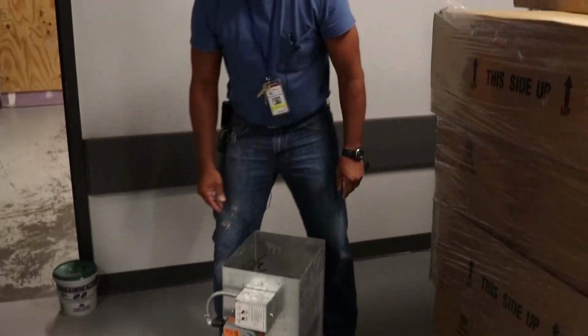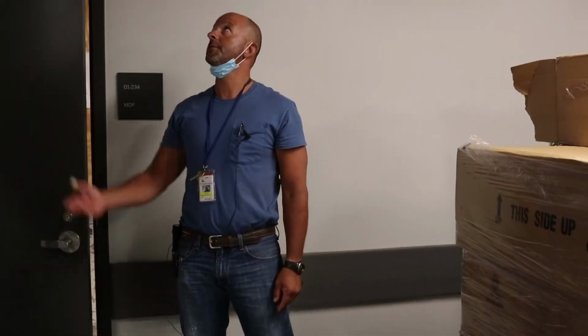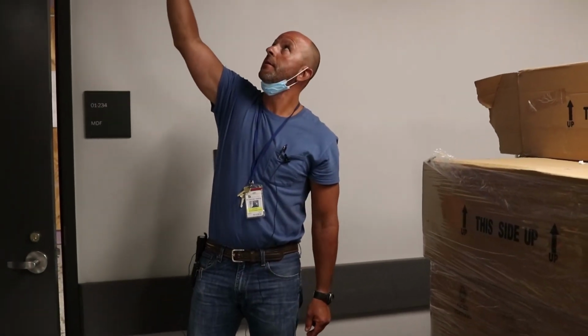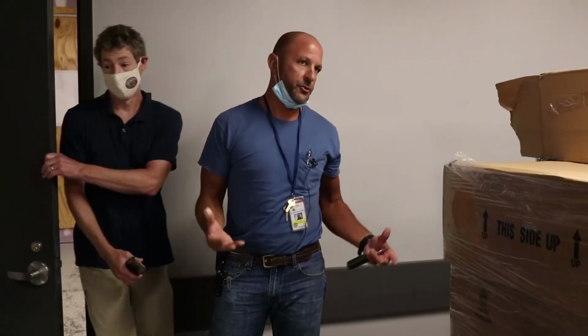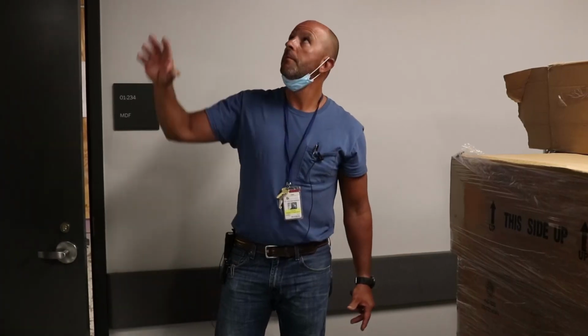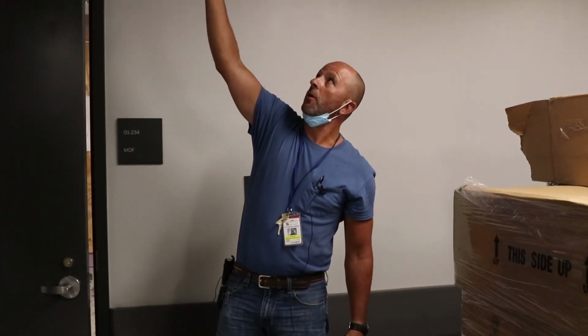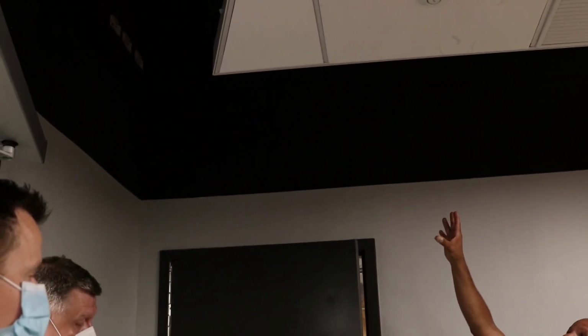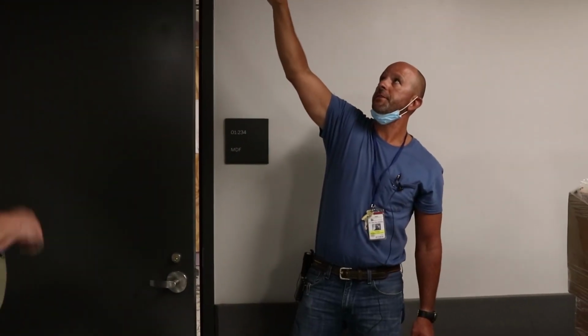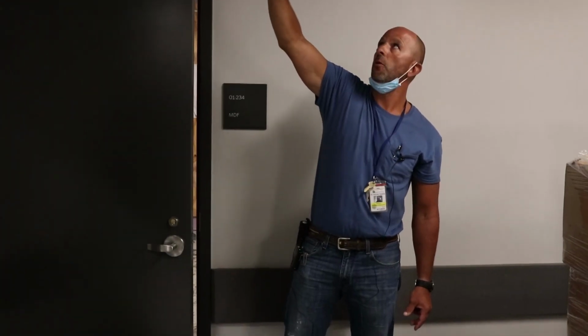Sorry, guys. Really not much maintenance to do on these things. Every one of these should have an access door located at the device, so you can open it up, look inside to see that the damper is open or closed. So if there's trouble, you should get it back at your alarm panel. This one here has an access door. I'm using this one, showing you this one. It's very similar to this one. It has all your fire alarm relays, which is probably part of another training, but based on the indication of lighting at the local relay, you'll be able to see if it is tripped or not tripped. It'll also report back to your panel.